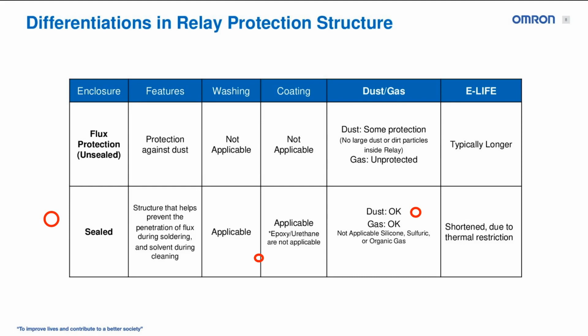The only issue that we may see with the electrical life on a sealed relay is it will be a little bit shortened as compared to an unsealed product because it will be holding all that heat within the casing. It doesn't have the ability to remove the hot gas from within. So we just have to consider that and look at the electrical life ratings for each product.